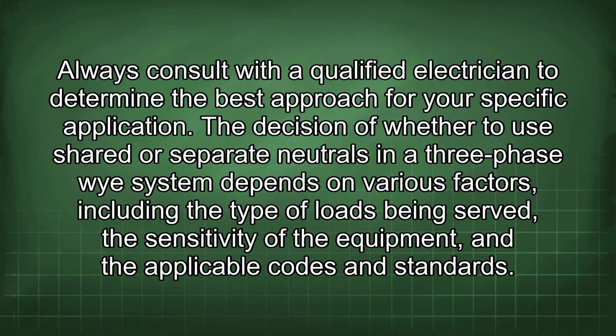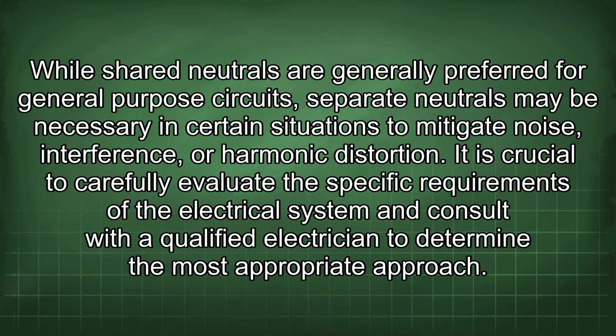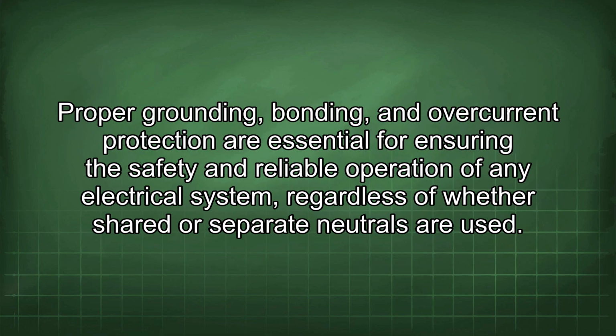The decision of whether to use shared or separate neutrals in a three-phase Y system depends on various factors, including the type of loads being served, the sensitivity of the equipment, and the applicable codes and standards. While shared neutrals are generally preferred for general-purpose circuits, separate neutrals may be necessary in certain situations to mitigate noise, interference, or harmonic distortion. It is crucial to carefully evaluate the specific requirements of the electrical system and consult with a qualified electrician to determine the most appropriate approach. Proper grounding, bonding, and overcurrent protection are essential for ensuring the safety and reliable operation of any electrical system, regardless of whether shared or separate neutrals are used.